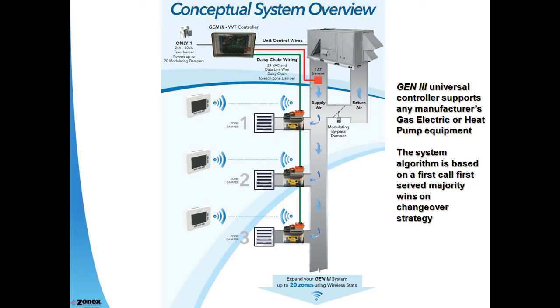We reviewed power wiring, but let's focus on the transformer for a moment, located at the GenIII controller. Note, only one 24-volt transformer is required to power all zone dampers in the system. This saves time and potential wiring errors if a transformer is required at each damper, as many other systems require. Simple wiring, easy operation, and the GenIII supports any manufacturer's gas, electric, or heat pump equipment.